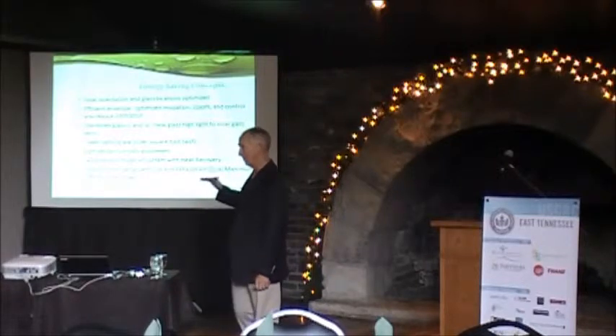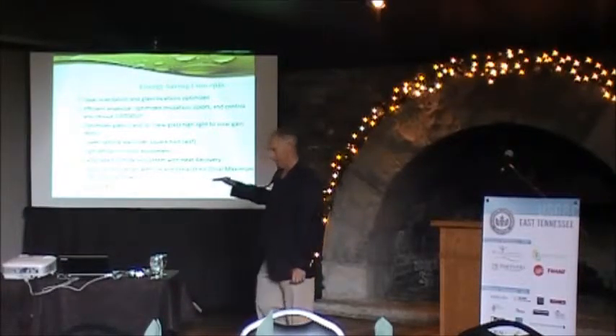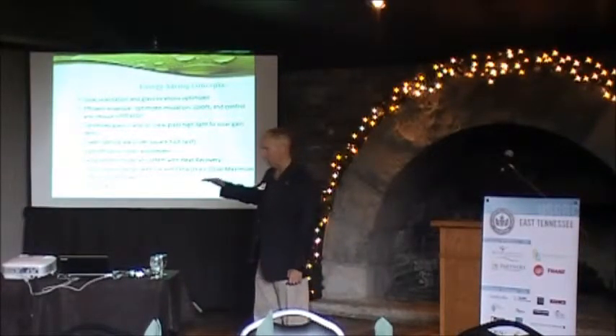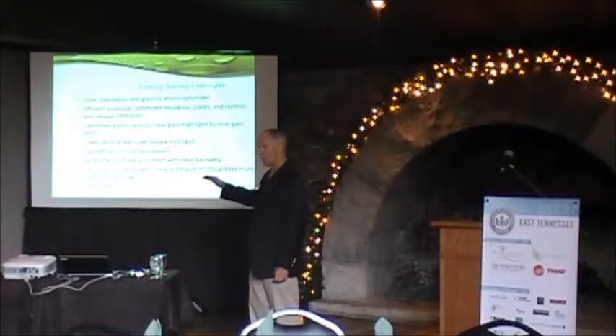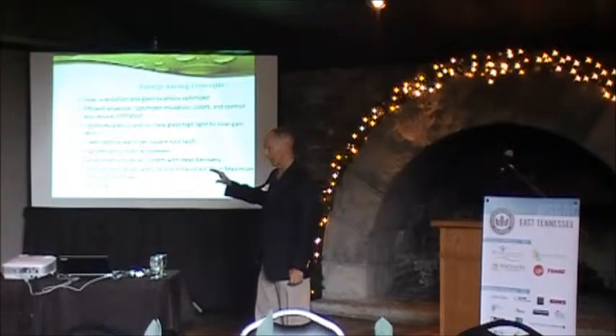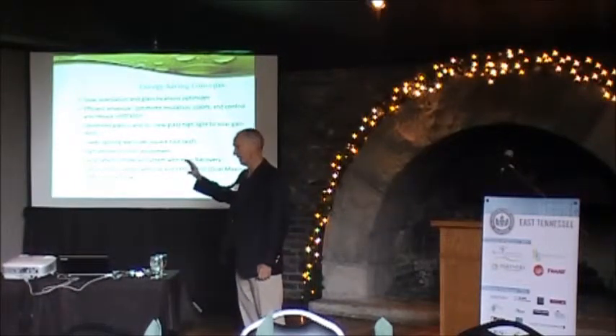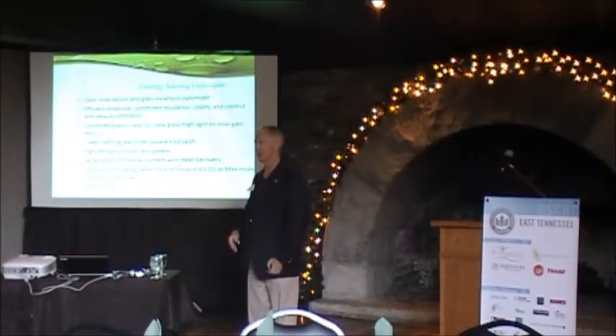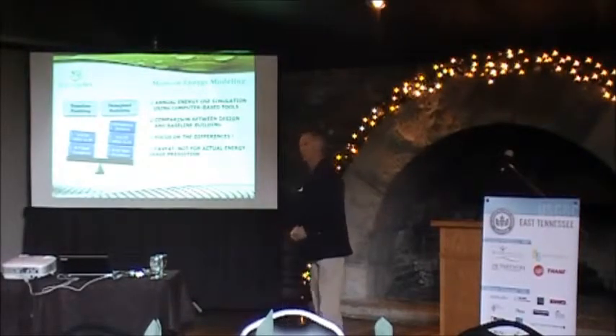Going back to the energy model: if your base building is 50% glass, well, the base building in the code model is set at 40% glass, because that's what the code requires. So if your actual building has 50%, it's like you've already got one arm tied behind your back. We had a project early on that was almost at the glass code limit because of this.